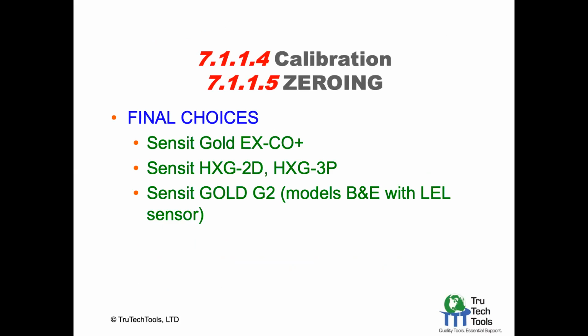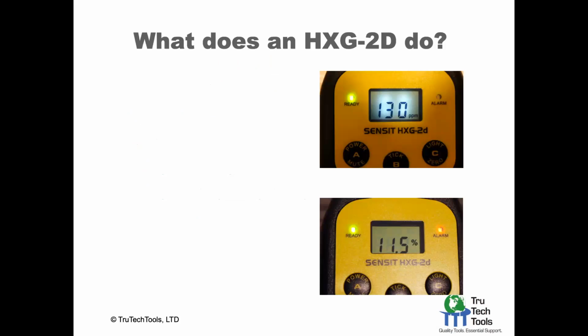And then calibrating and zeroing, the final choice is the last step in the standard. Some of those other products have this ability, but they don't have the other requirements that led to this point. So out of this full list of products, many of them are more advanced products for the utility and the fire department industry, but the basic one, the Sensit HXG-2D, that just does pretty much dedicated purpose combustible gas measurement leak detection, that was the winner, the survivor.